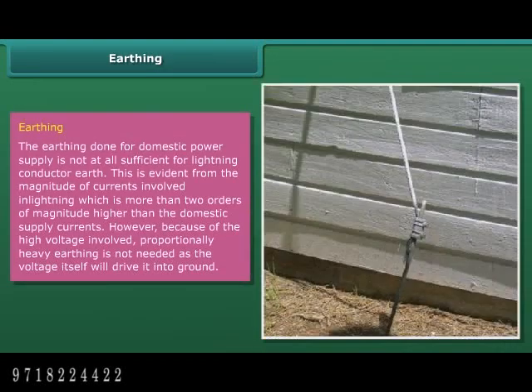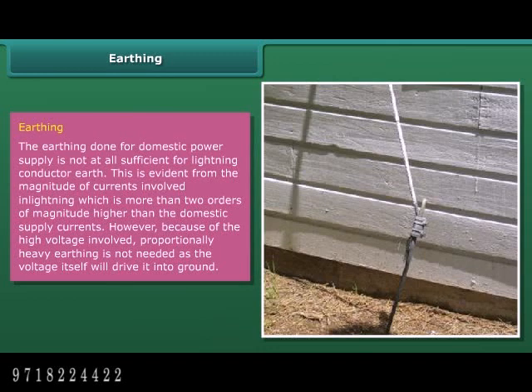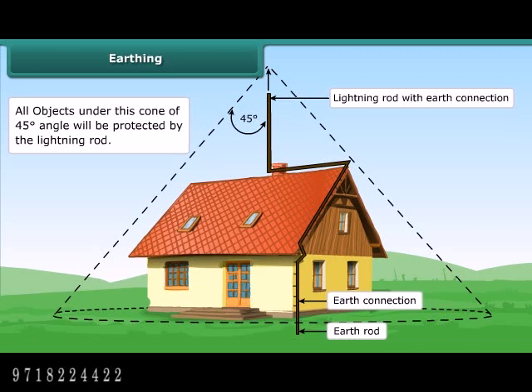The earthing done for domestic power supply is not sufficient for a lightning conductor earth, as the magnitude of currents involved in lightning is more than two orders of magnitude higher than domestic supply currents. However, because of the high voltage involved, proportionally heavy earthing is not needed, as the voltage itself will drive it into the ground. The cone of protection describes the volume of protection offered and provides a simple graphical tool for installing a lightning conductor protection system.